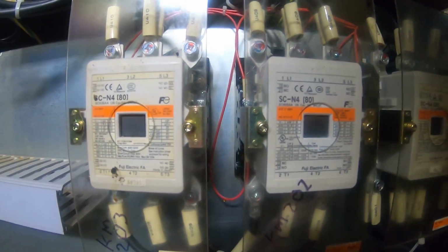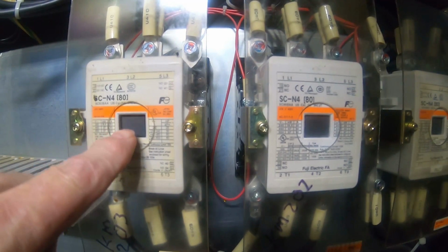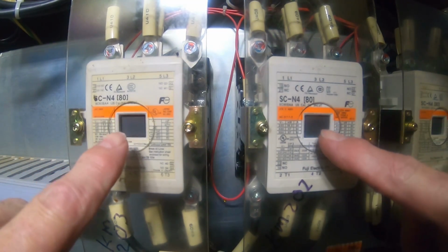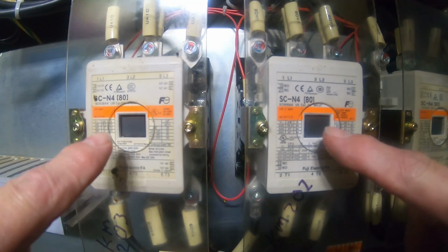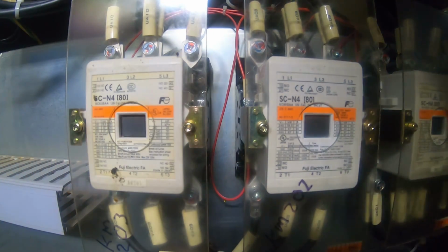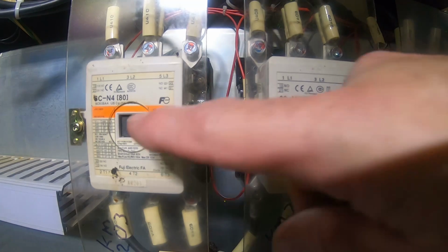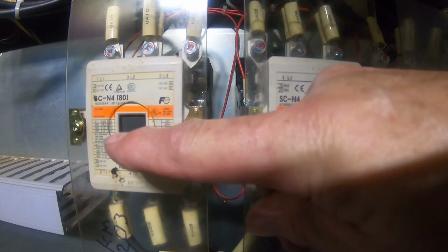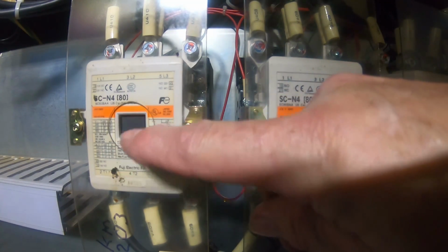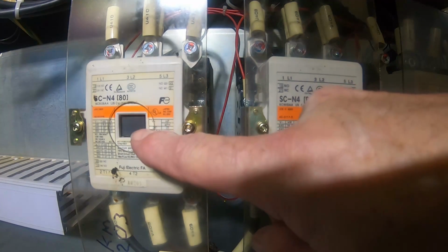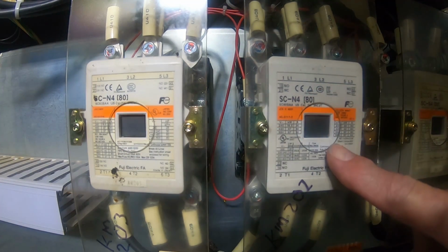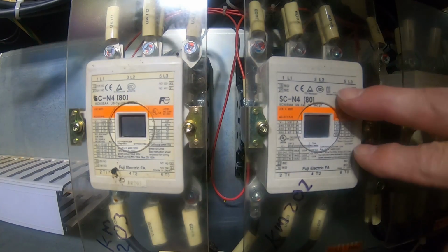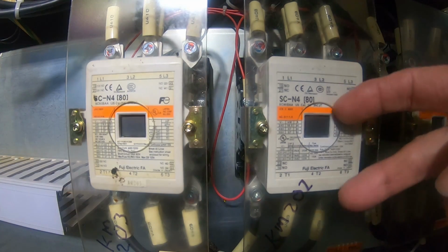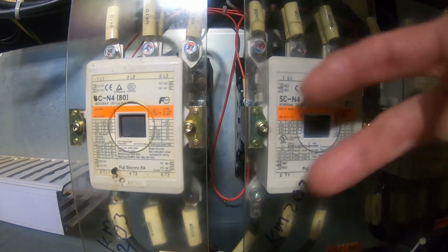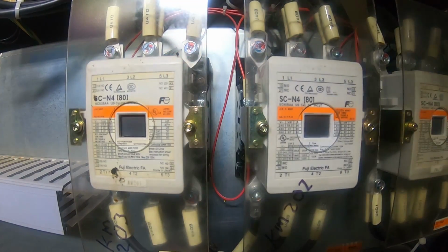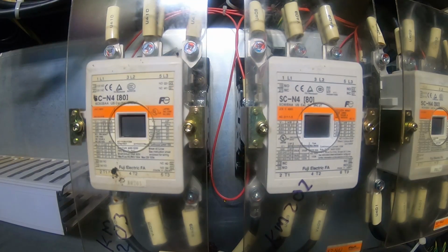If I go to start the machine, you'll see it release this relay, and it's supposed to pull in this one. Let me go start that and duplicate what I showed you on the control, and you'll see it released this one, and then it'll pull it back in and release it, because it's supposed to release this relay and engage this one — this is the delta windings, the high speed side, and this is the low speed side here. So I'm going back around the machine.